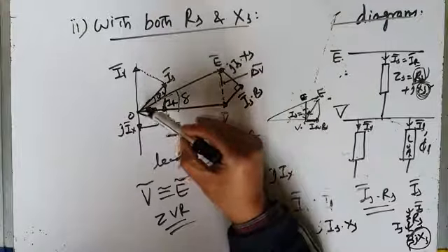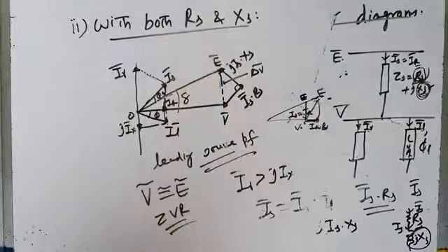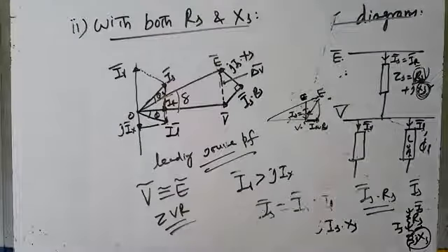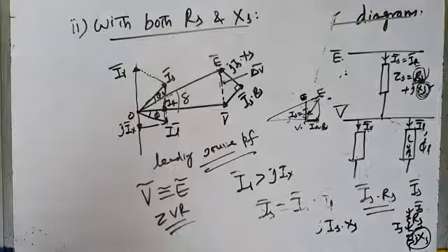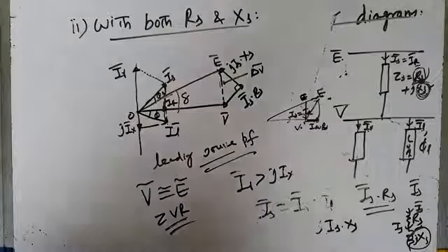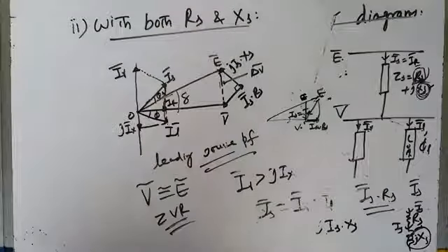It was made possible only when source current, that's current flow drawn from the source, is at leading power factor. So this is how this phasor diagram clearly shows how we can use the compensator as a voltage regulator for achieving zero voltage regulation, ZVR. But if you have to make a choice, you have a compensator, say D-STATCOM, you have to either use it for reactive power compensation, that is power factor correction, unity power factor operation, or as a voltage regulator for achieving zero voltage regulation.